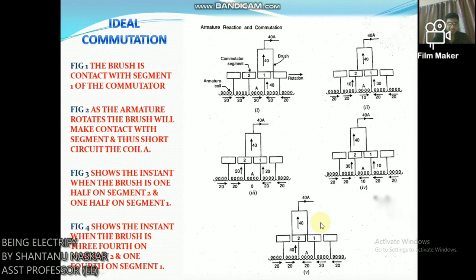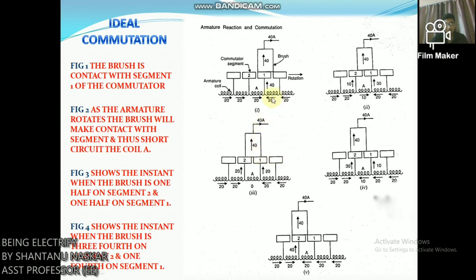In figure 1, the brush is in contact with segment 1 of the commutator. Segment 1 conducts a current of 40 amperes to the brush: 20 amperes from coil A and 20 amperes from the adjacent coil, as shown in the figure. Coil A has yet to undergo commutation.